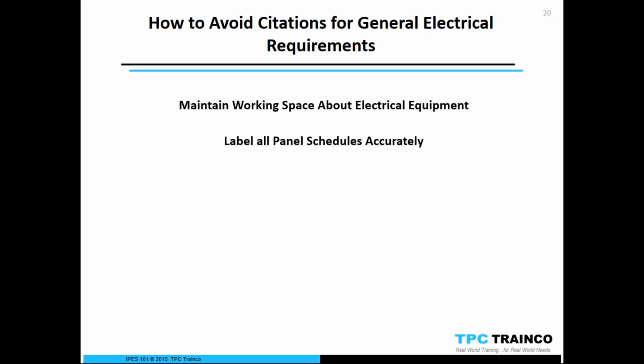In the last company I was in, they had a citation that cost them $50,000. And they looked at me and they said, what could we have done? I said, you could get a circuit tracer, trace those out. It sends a signal on your conductors, and then you have a receiver to pick that signal up. It really can be very beneficial for you. OSHA wants to make sure that if we are de-energizing something, if there's an accident and we have to get the equipment shut down quickly, that these panel schedules are all labeled 100% perfect.